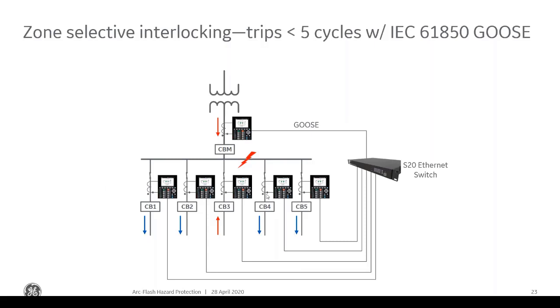The other way of doing this is to hardwire those blocking signals from the relay back to the main relay. Obviously, the disadvantage of doing that is a lot of wiring required, a lot of cables that you've got to run. And the other thing is maintainability of that system. If there's a problem with it, troubleshooting it, you might not even know about it until there's an event and then it fails to operate. With the communication medium using GOOSE, it's constantly monitored, so any disruption or break in the communications, you know about it right away. And the wiring is very limited.